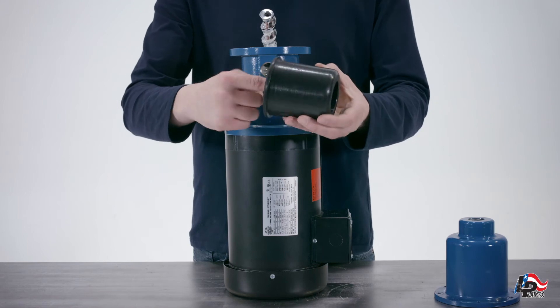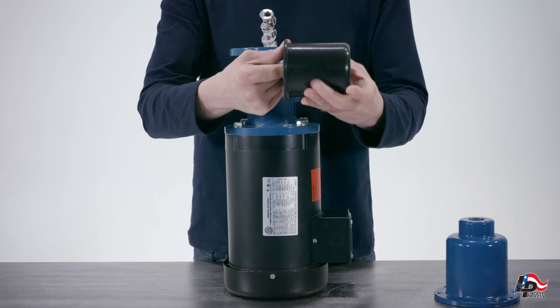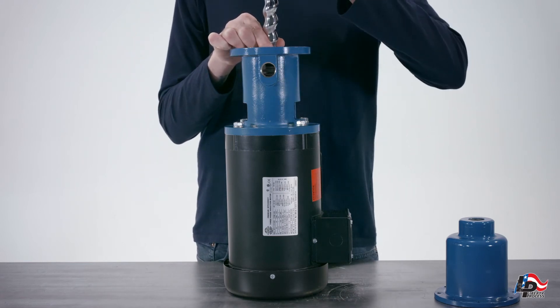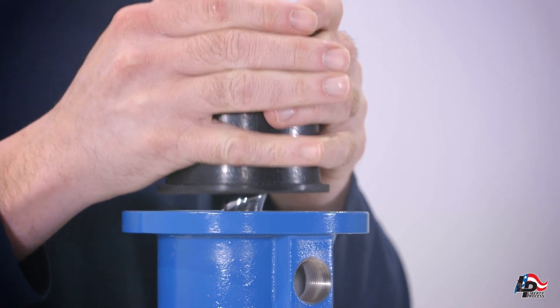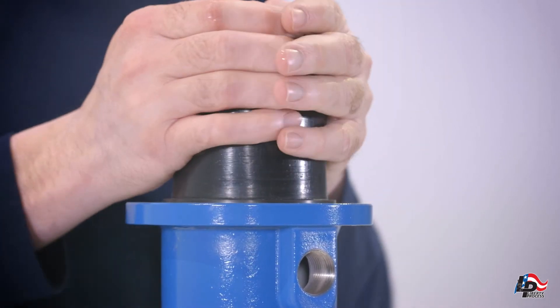Lubricate the rotor and interior of the stator with liquid hand soap. Slide the stator open side down onto the rotor and push down. The stator will seat itself into the channel on the discharge casing and will act as a seal.